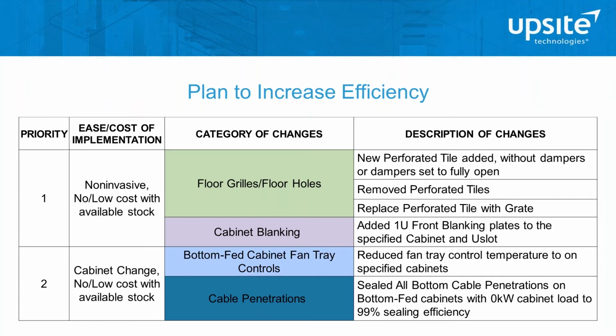I think the interesting point being revealed here is that it takes something as sophisticated as the engineering simulation you're doing, along with the calibration of that simulation, combined with the very fundamentals of airflow management—sealing cable openings and blanking panels—it takes a combination to achieve high efficiency in a facility.